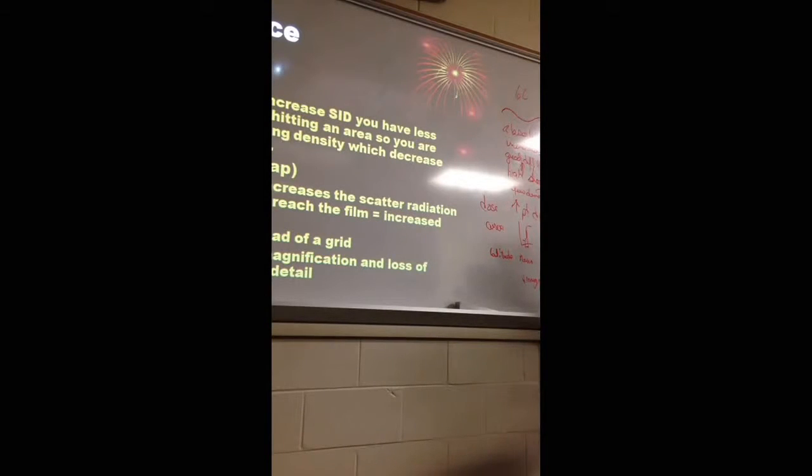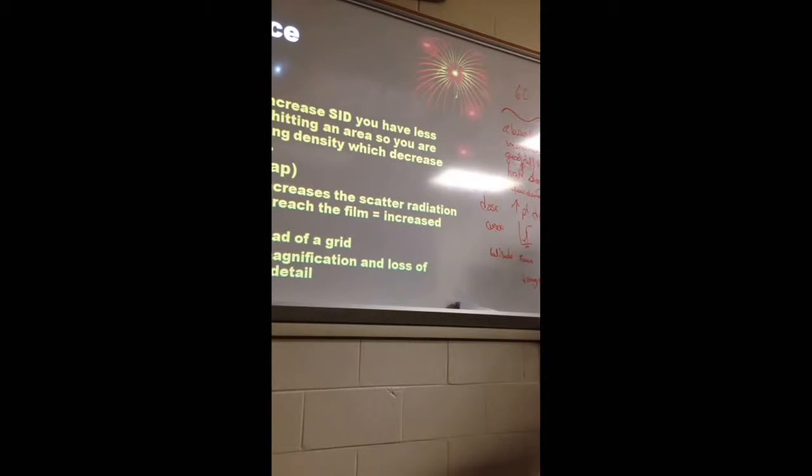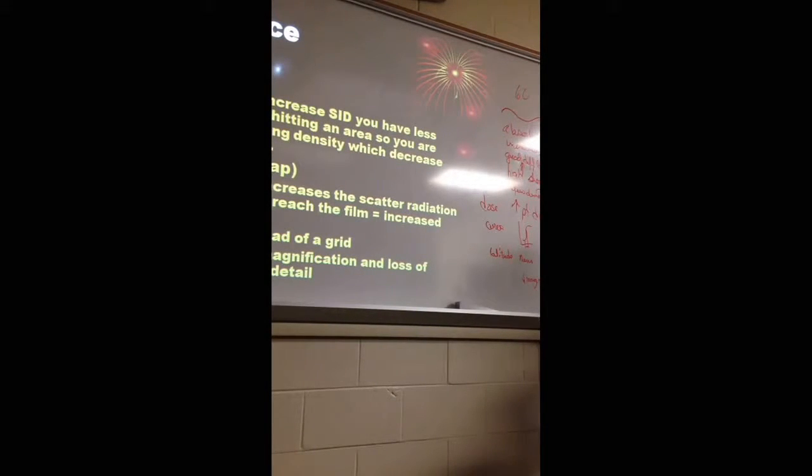So in reality, if you double your distance, we're at 36 and we go to 72, we double our distance, right? What happens to the intensity at the film? It goes down. By how much? Half. Yeah, 4 times. By a factor of 4, which means it's reduced by 75%. So we now have a quarter of the intensity. So now that image is totally underexposed, so it's going to have a decreased contrast, right?